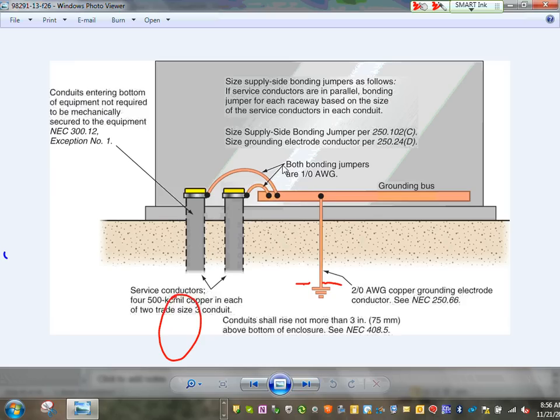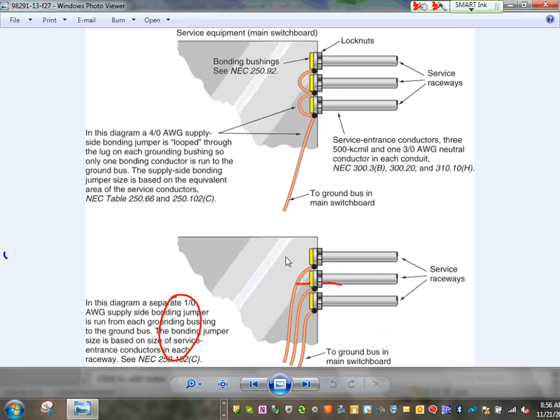Bonding the conduits, all the conduits, if they're rigid coming from underground, Adam, they have to be bonded. This is called the supply side bonding jumper. I will spend more time on it when we go into the industrial because that's when we parallel. But it's sized exactly like the main bonding jumper. Same thing, guys. See all these conduits, they're coming here. If they're at the service, and these are concentric and eccentric knockouts, you have to bond all these conduits. You see how they bond? Either daisy chain them like this, Karen, or you can take them one at a time.